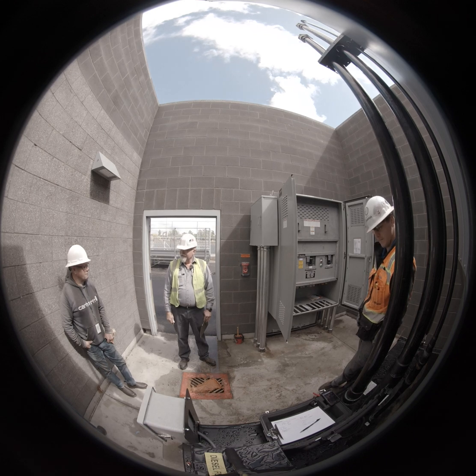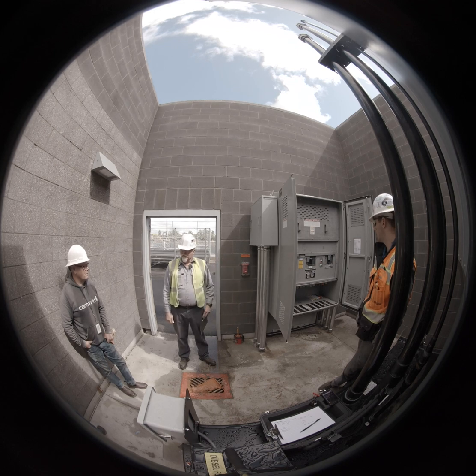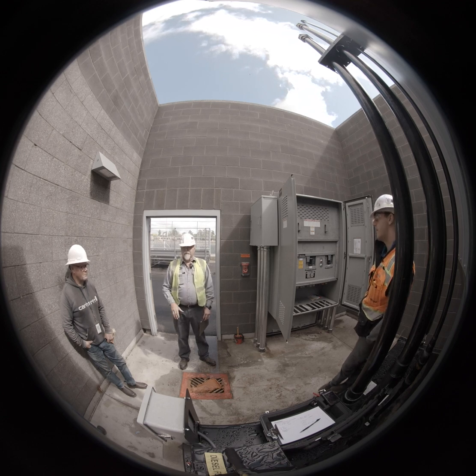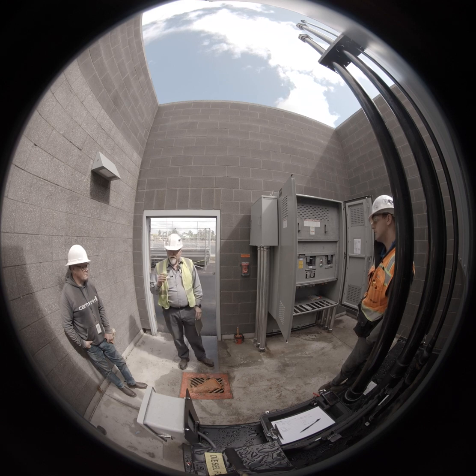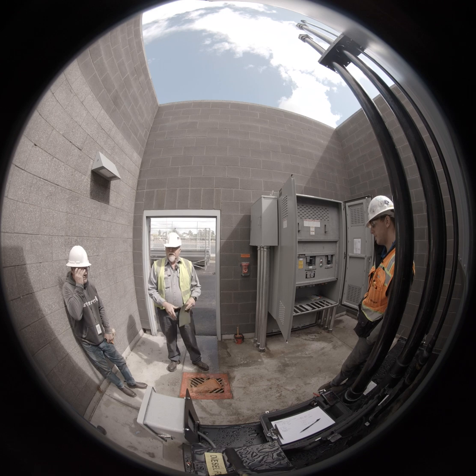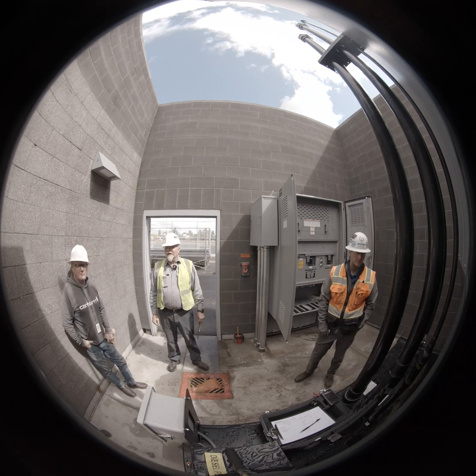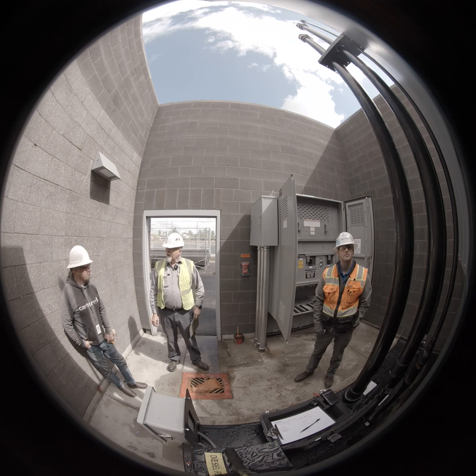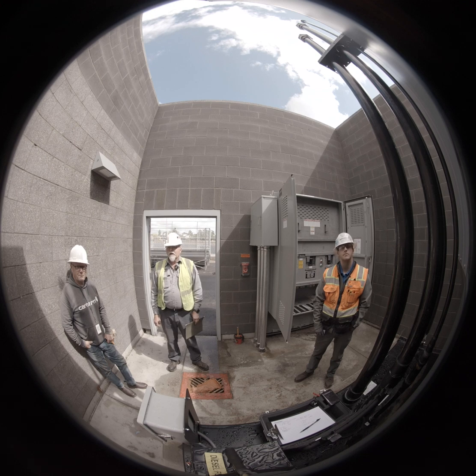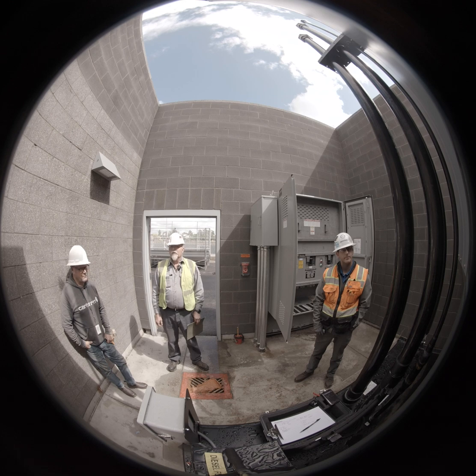The system incorporates the backup generator set, the 3 transfer switches, the tap box for load bank / temp gen, and the fire command panel. I'm going to start out with a basic overview of what we have here with the gen set. This gen set is an MTU onsite energy Rolls-Royce machine manufactured in Mankato, Minnesota. This machine is powered by a 13-liter John Deere engine with a Marathon alternator end and MTU electronic controls.